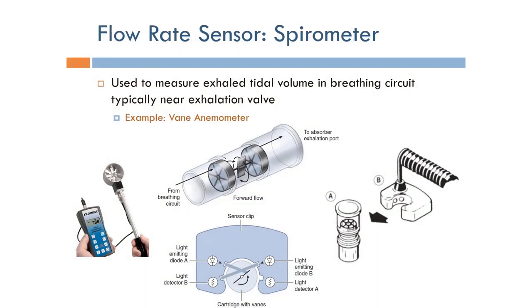Another idea to compute the flow rate is using something called a spirometer. The spirometer is used to measure exhaled volume in the breathing circuit, typically near the exhalation valve. There are several types of this particular sensor.